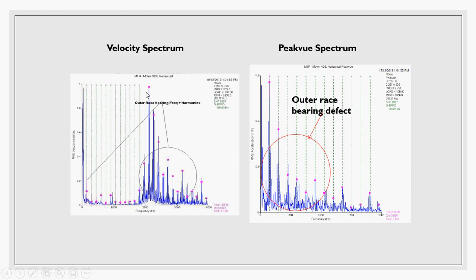The velocity spectrum is indicative of what could be a third-stage bearing fault. The PeakVue spectrum shows the outer race bearing defect with many harmonics at the bearing defect frequency for the SKF bearing 6307. We'll talk more about bearing fault stages in the bearing fault video series I started, covering all stages — outer race, inner race, cage, and rolling element.